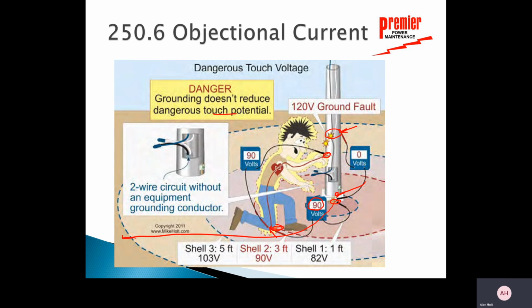So in this particular case, shell 1 was 82 volts, shell 2 was 90 volts, shell 3, 5 feet out, was 103 volts. So without that ground going back to the actual ground of the service entrance, I can have some dangerous step potential voltage increases here. So this ground needs to go back solidly to the service entrance panel, to that ground location, so I have a direct path. Anything that's going through the earth can mean a potential hazard for me.